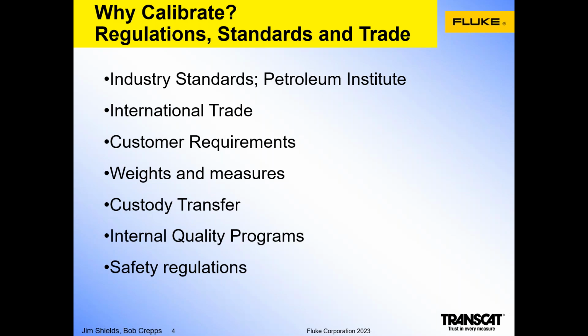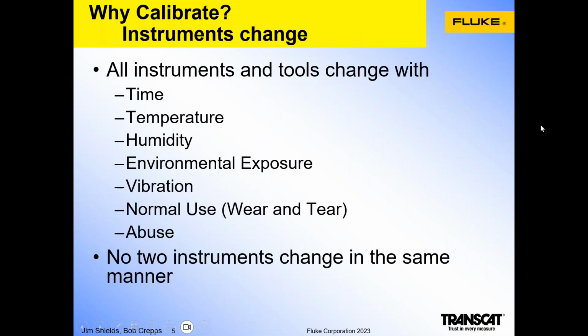And then, of course, last but not least, safety regulations, devices that are part of a safety and shutdown system that are critical to the safe operation of the plant and the safe shutdown of the plant, often require that those instruments have significant calibration records that can be reviewed by an OSHA auditor, for example. They're also important for the safety of the personnel in the plant and the public at large that lives in and around these plants that could potentially be affected by an unsafe incident or event that could occasionally happen at these plants. Ideally not, but sometimes that happens.